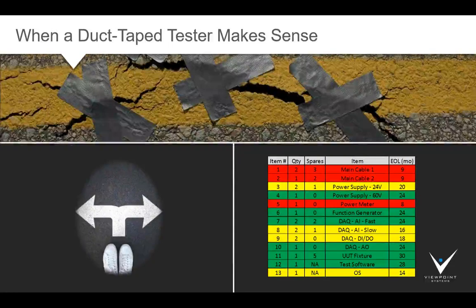Also, you should match the life cycle of the tester with the life cycle of the products being tested. For example, there's no point in upgrading the tester if the only product you're testing is not going to be manufactured next month. The point is that thought and planning to consider how long you need each component to last will help prioritize your upgrade path. So often, a little duct tape makes great sense.